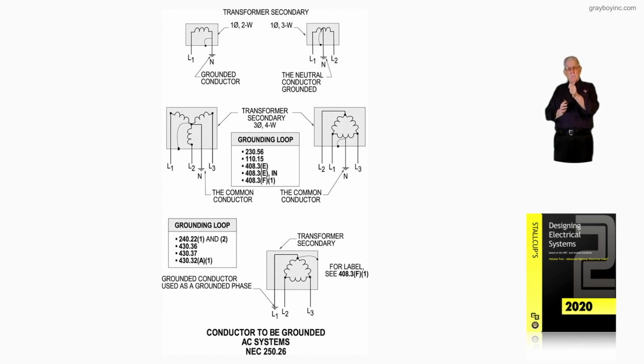But if you have that transformer at the bottom, right above the caption, conductor to be grounded AC systems, there's your sections that regulate it. And you can fuse it like at a fusible disconnect for an irrigation pump. You could fuse it if you provided overload protection in accordance with the sections that you see there. Or you could have a 3-pole breaker that would disconnect it. But you've got to follow the rules to 240.22, 1 and 2, along with the other sections that you see there for that type of system. Now, I believe that this illustration, 16-30, will illustrate the conductor to be grounded when you have an AC system in accordance with NEC 250.26.